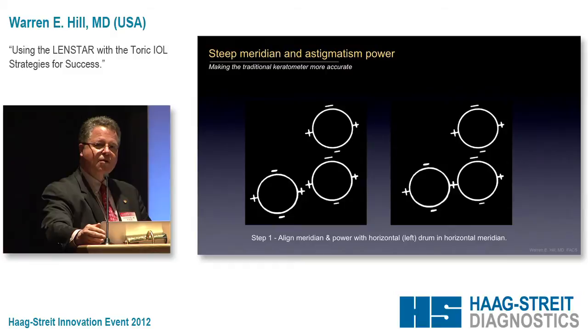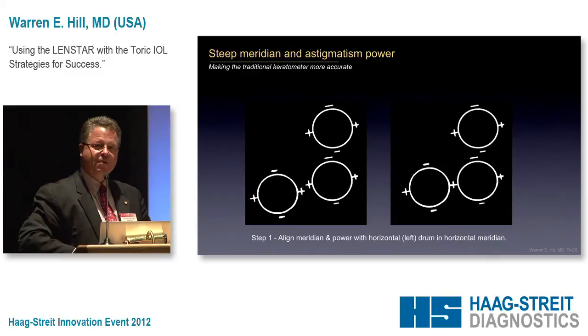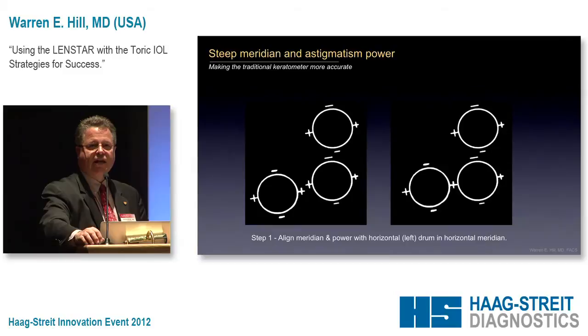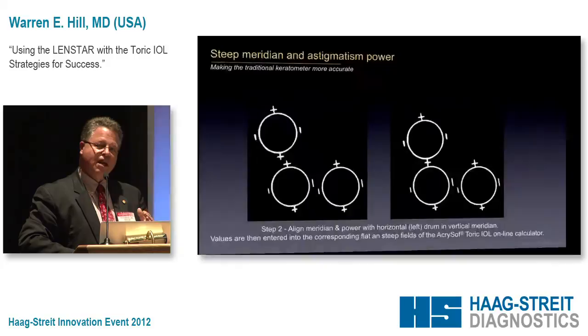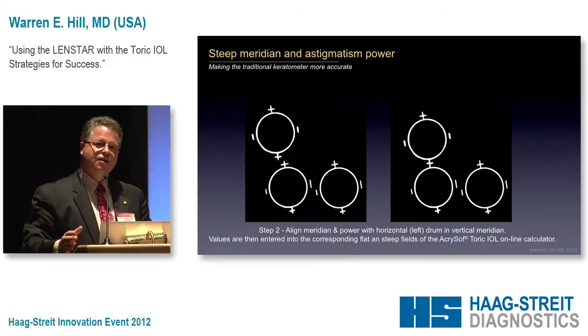Let's talk about the humble keratometer, because this actually has some meaning in terms of the LENSTAR. The keratometer is not a really accurate device, especially for the low astigmats, but it does allow us to take our time. With an automated keratometer, you push a button — it's like a digital camera, and whatever it does at that moment, that's what you're stuck with. With the manual keratometer, you can take your time, line up the meridian, and determine the power. But trying to get all those little floating rings to stay the same is like getting three cats to walk in a straight line. So take the horizontal drum, do your measurement, then rotate that drum 90 degrees — now you've thrown out anything to do with calibration, because what we're doing is looking for the power difference between meridians.